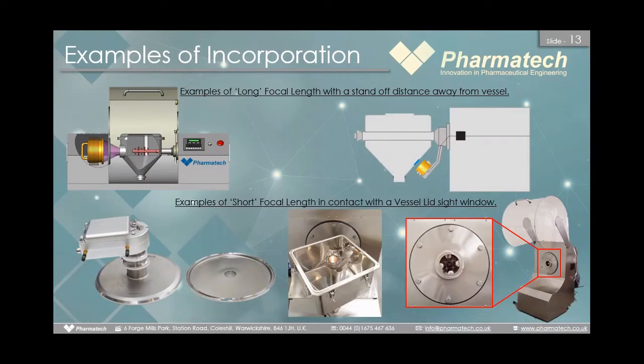This is just a few more images of examples of how it can be integrated into vessels. The top left one here shows a long focal length with an agitator, so it's effectively a double-sided drive unit. This was to allow continuous sampling, but with a long focal length, so the actual device rotates at the same time as the vessel, with all communications running back through a slip ring. Or for the short focal lengths, you've again got lid attachments. This is a V-shell lid in the bottom left. You can run a short focal length through a stub axle, or even run a probe through a stub axle if needs must.